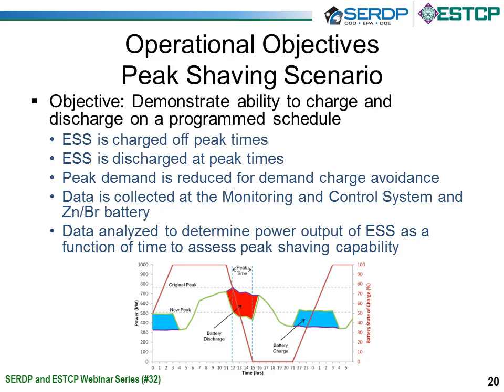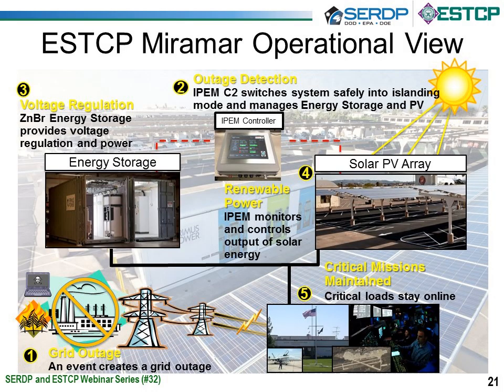Another secondary objective for this particular program, because we're trading the ability of energy security of backup diesel generators as a lower cost alternative, was the ability to leverage energy storage for operational cost reduction, because you can use the assets frequently throughout. They don't only have to be used for emergency power. We were trying to showcase that you can use the energy storage for peak shaving capabilities to potentially generate some operational cost reductions. So basically, your demand load shifting by charging at night and then discharging during peak times during the day.